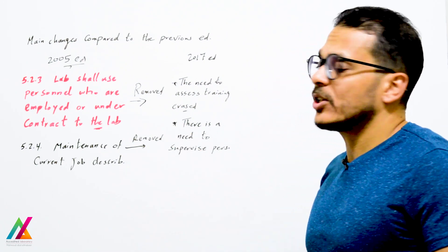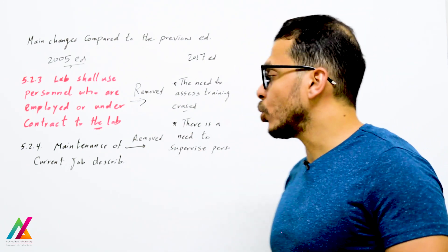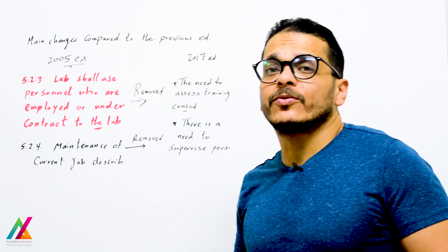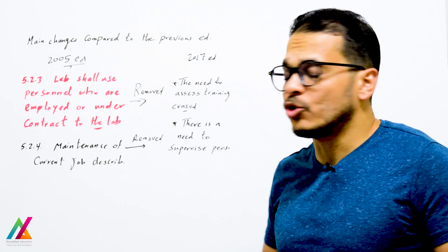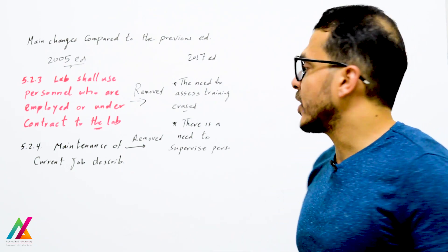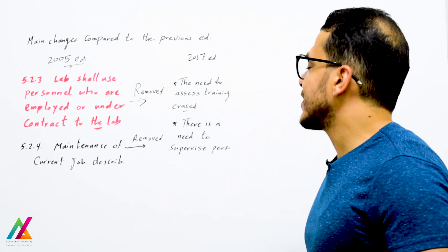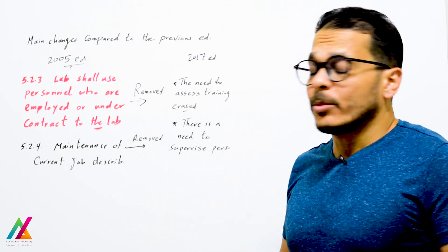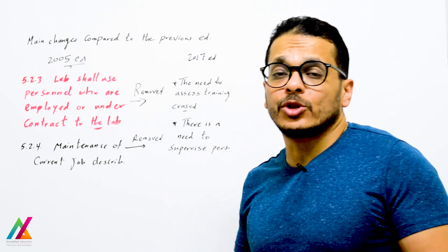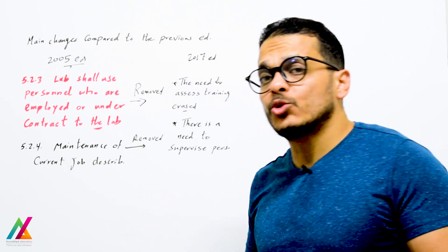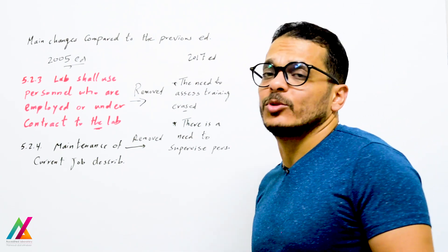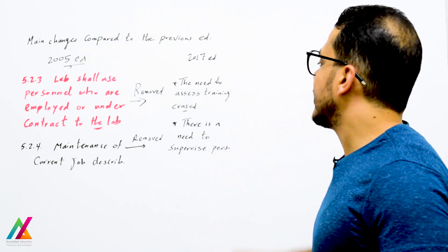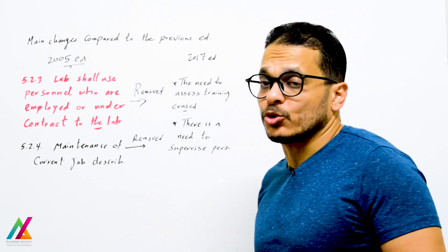Comparing to the 2005 edition: clause 5.2.3 requiring labs to use personnel employed or under contract has been removed in 2017. Clause 5.2.4 on maintenance of current job descriptions has also been removed, though you may still use a job description form or find another suitable approach. The need to assess training has also been removed, but you will still prepare a training procedure and can add training assessment to it.